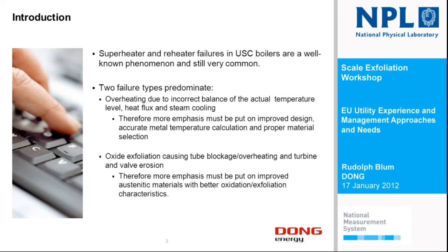were equipped with relatively low alloyed materials compared with the actual steam temperature. So when we took samples out of the superheaters and even part of the reheater pipe system, we had thicknesses far above 0.5 millimeter, something up to 1 millimeter, in oxide. And then I think it's fair that now and then you have a little spallation. But we could catch all these things in the sieves, and we never saw erosion problems from oxide in the high pressure part of the turbine.